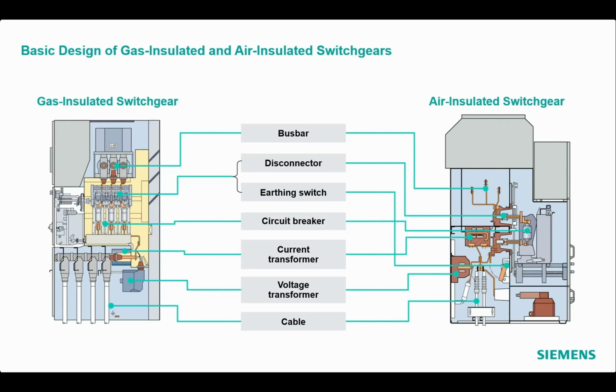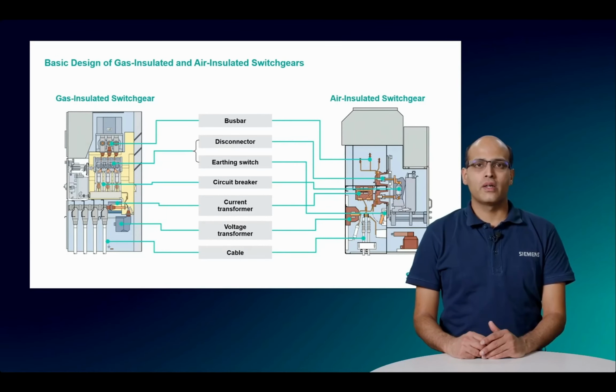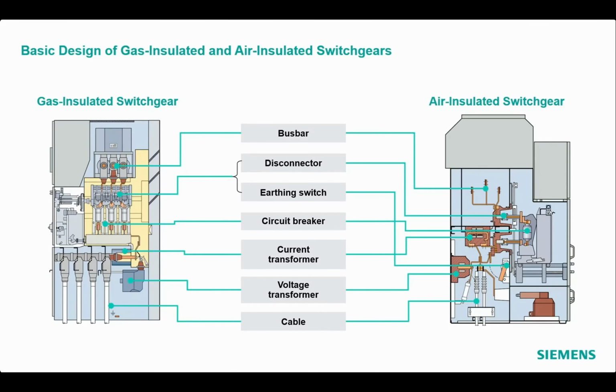As next, we have the current and voltage transformers. The current transformers, in short CTs, help in measuring and monitoring the electrical currents. They transform the higher currents to a lower current level, which can be used by protection relays to detect overcurrent and short circuit currents and perform protective actions. Additionally, the CTs can be used for bill metering and to measure energy consumption as required.